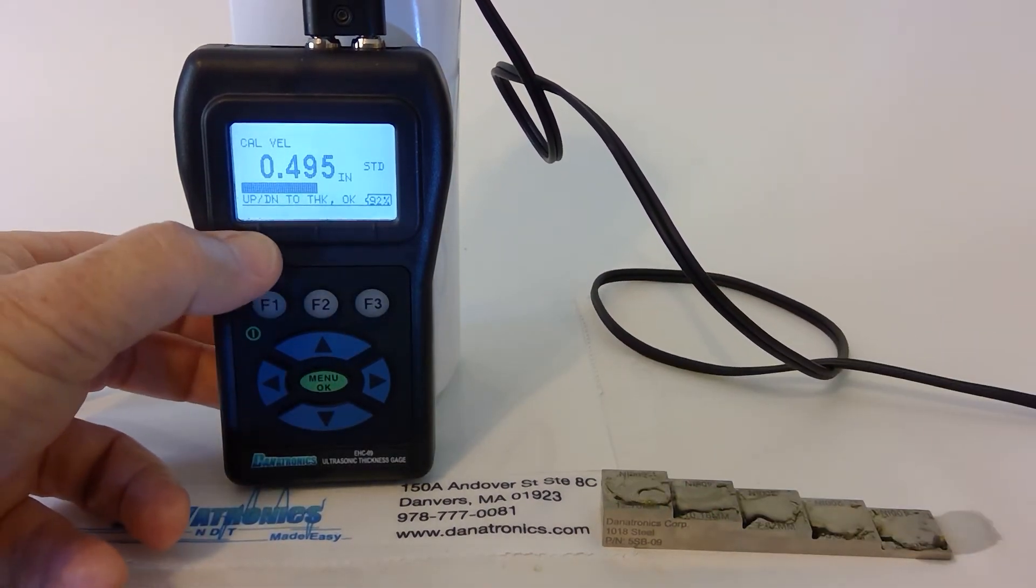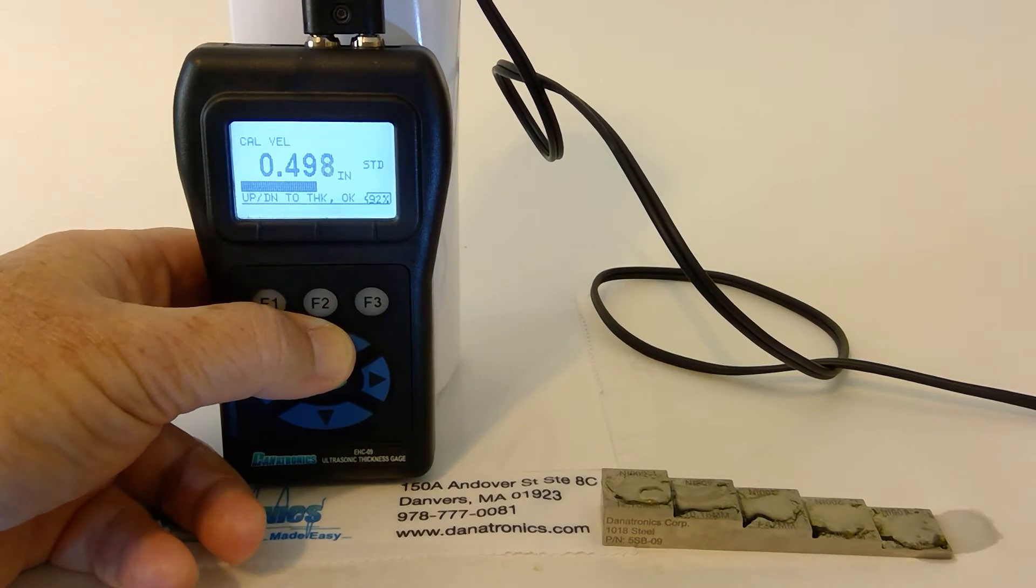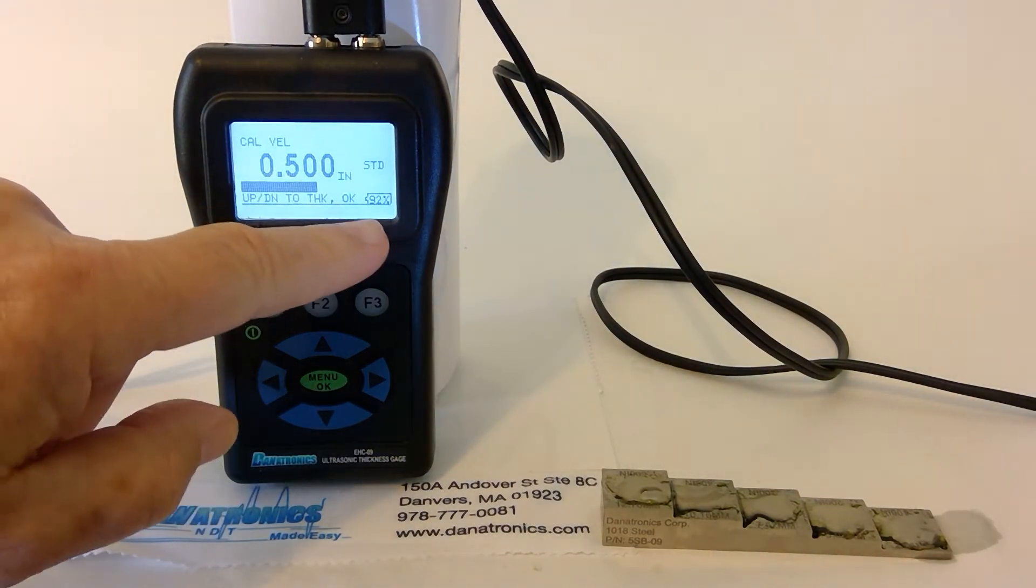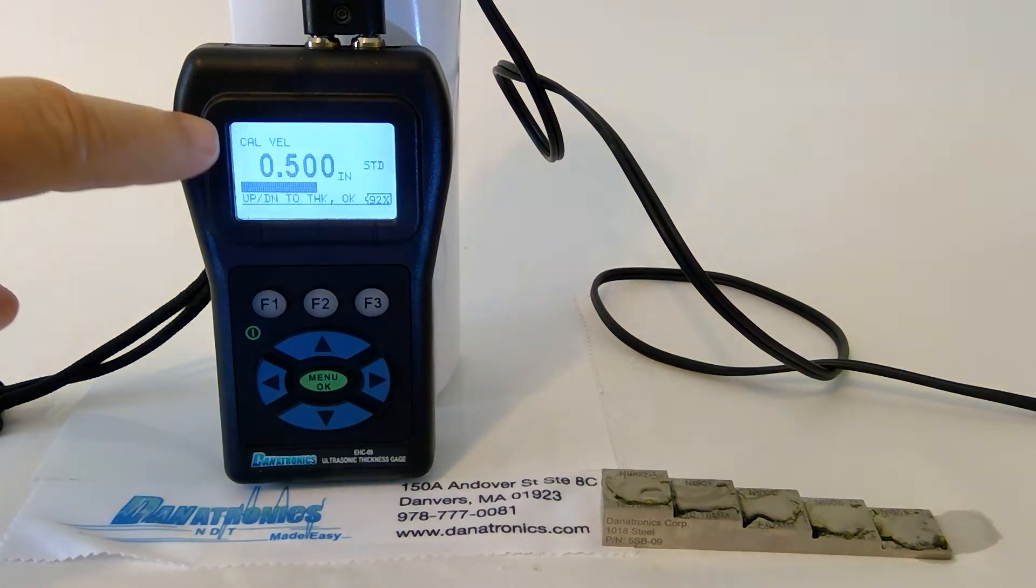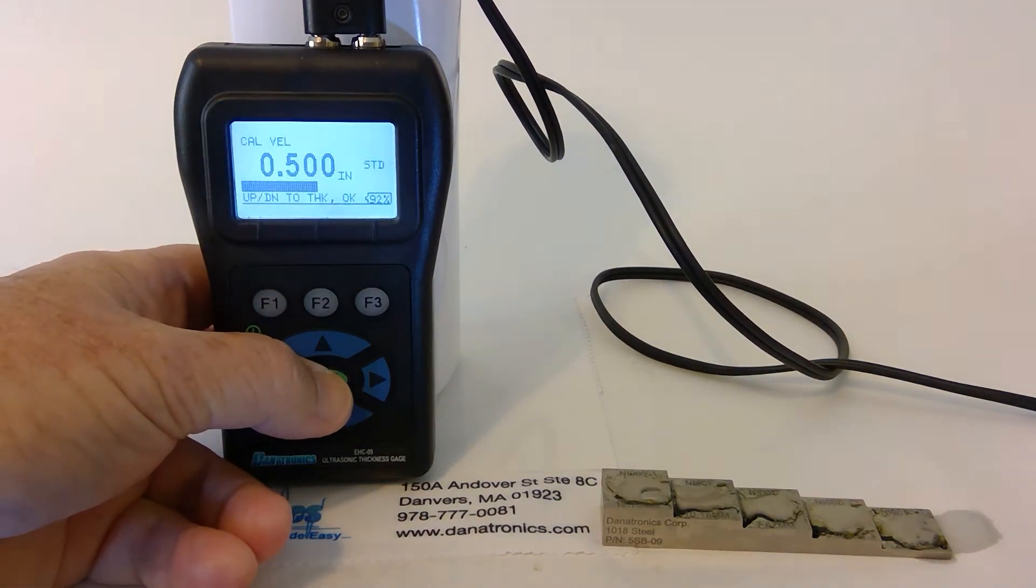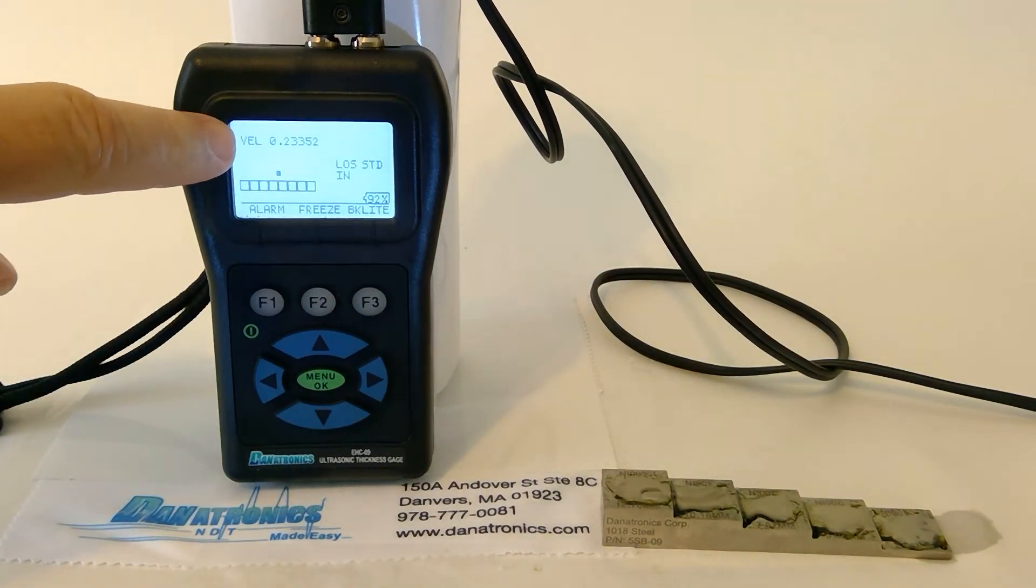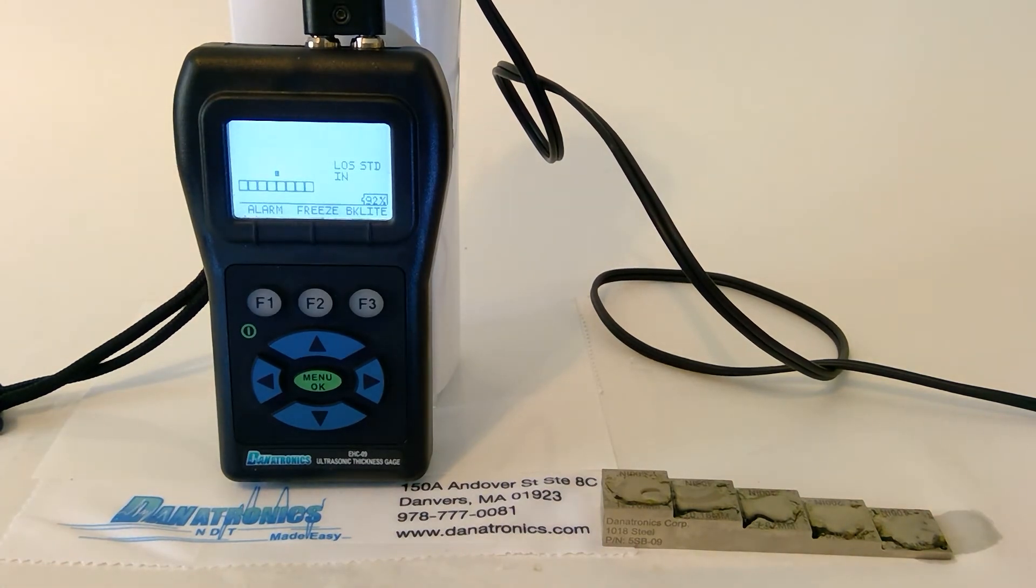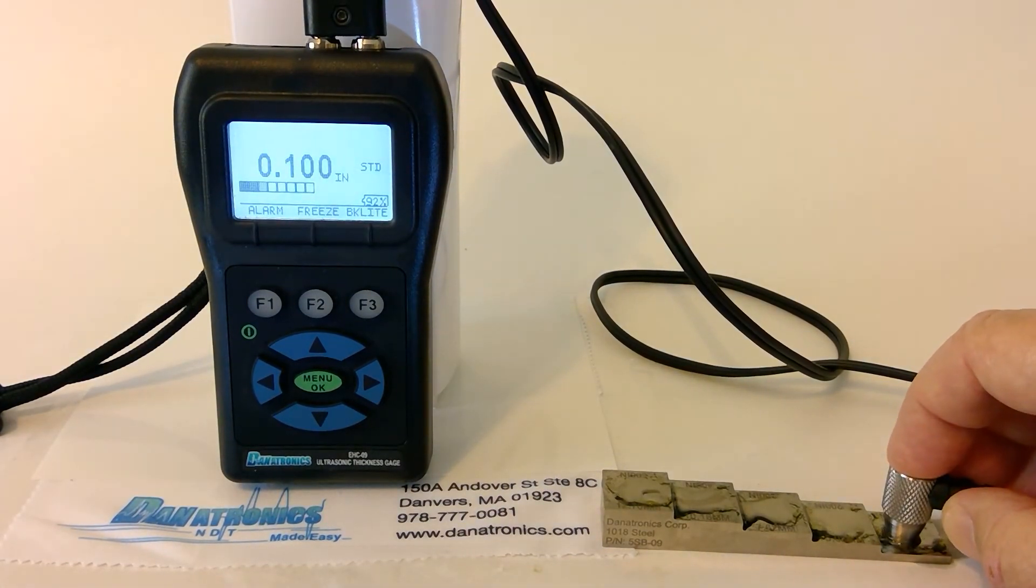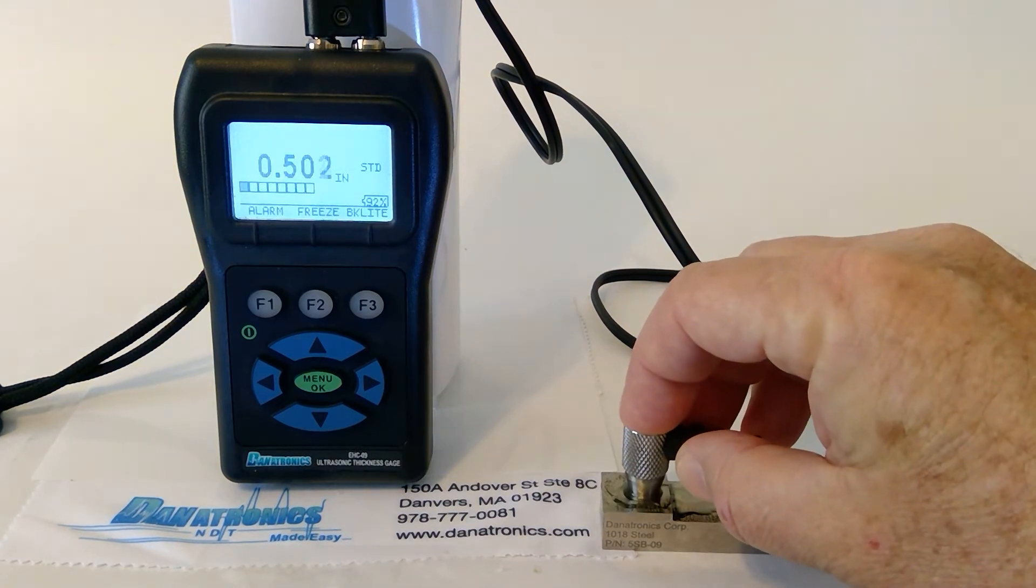Now the up or down arrow key to 500 thousandths. Then we press OK. And if you'll notice at the top of the screen, it will calculate the velocity located here. And now we are calibrated.